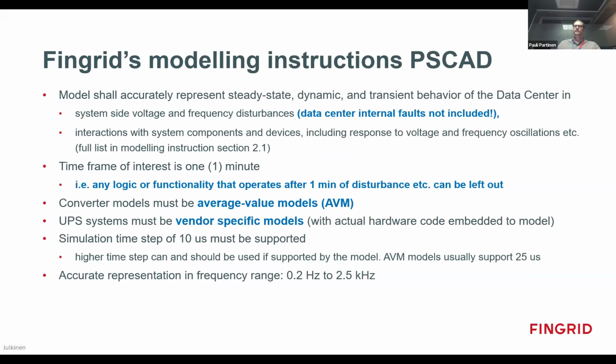This slide presents key topics from the PSCAD requirements. We expect the model to behave correctly in all scenarios seen from the connection point. We are not that interested in what happens in, for example, internal faults. For PSCAD, it is very important to model all elements that could cause interactions with the system components and devices. The time frame of interest is a 1 minute simulation. If there is some kind of control logic that turns on after 1 minute, it can be neglected.